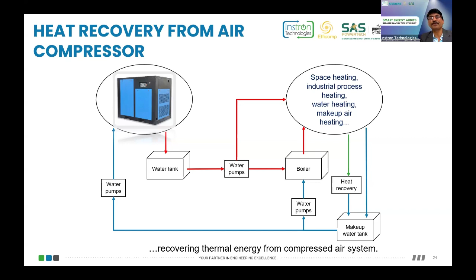So if we recover that heat, we can see how high the value can be. With compressed air, if heat recovery is done, we can use it to preheat water for a boiler or for space heating or any other industrial purpose where we want hot water up to 80 degrees centigrade. So heat recovery is one of the biggest areas for CO2 reduction. It will not affect the compressor power, but it will have a direct impact on your fuel, which is being used for steam. If you are using steam for heating purposes, or electrical heaters for water, that can be done with the compressor itself. So it is one of the major areas of CO2 reduction in a system.